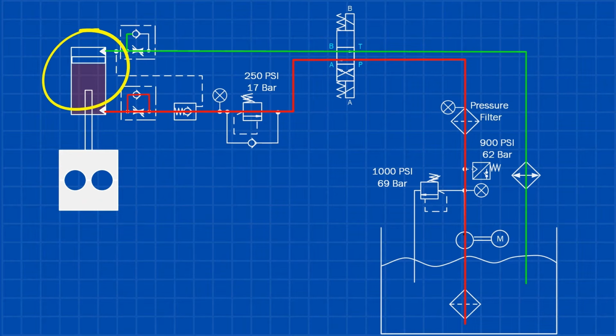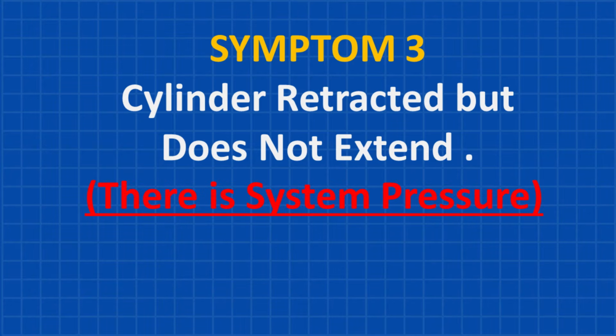In rare cases, the piston could actually be separated from the rod. When this happens, shifting the valve might make the piston retract, but the rod stays right where it is, giving the illusion that nothing is moving. To troubleshoot, start by replacing the directional valve. If that doesn't fix the issue, it's time to replace the cylinder. Symptom 3. Cylinder retracted but fails to extend, and there is system pressure.